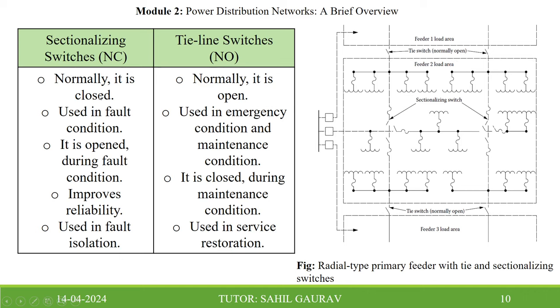Sectionalizing switches, we know that these switches are normally closed type, and tie line switches, these switches are normally open type. So NC means normally closed and tie line switches means normally open. And sectionalizing switches are used in the fault condition, while tie line switches are used in the emergency condition and maintenance condition.